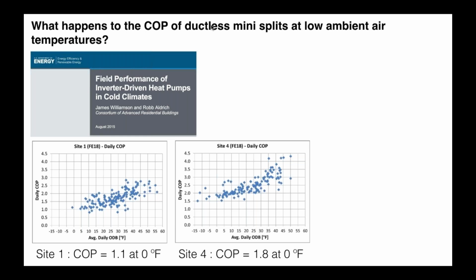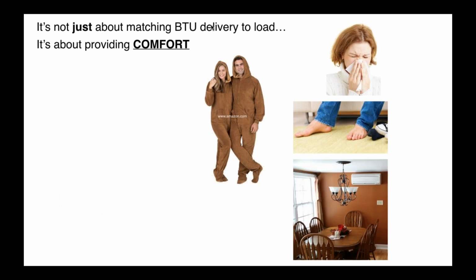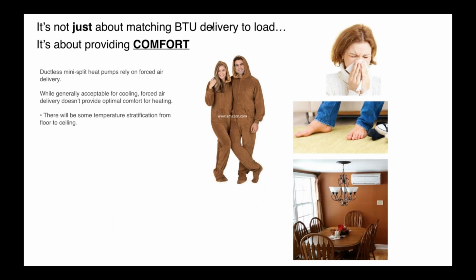Yeah, the low ambient heat pump designs with the EVI refrigeration systems, they can work pretty good at sub-0 degrees Fahrenheit, but they're not producing COPs up in that 3 or 4 range. Think about what I think is a good performance. If you're producing 120 degree water when it's 0 degrees Fahrenheit outside with a COP of 2, you've got a good heat pump. Okay. Again, comfort.